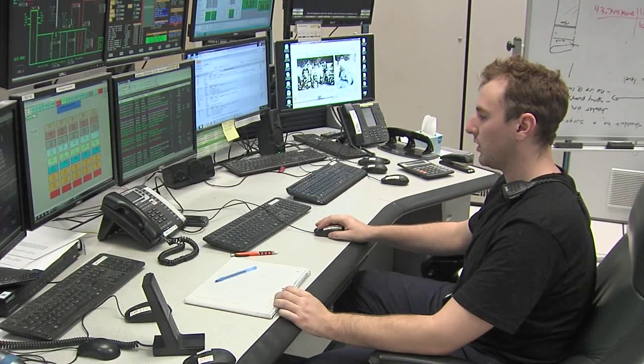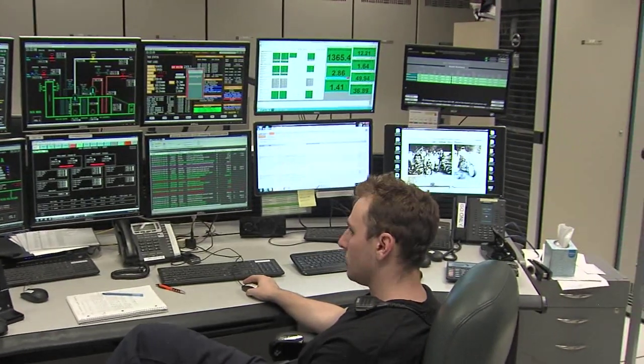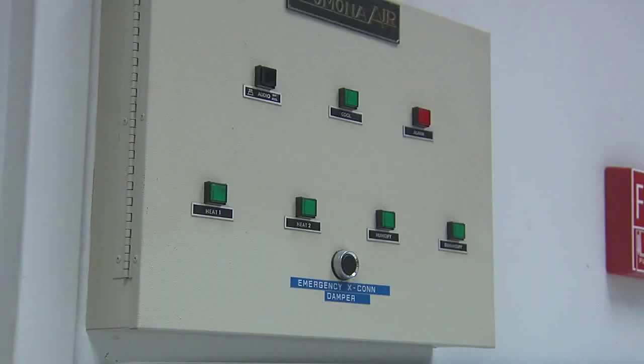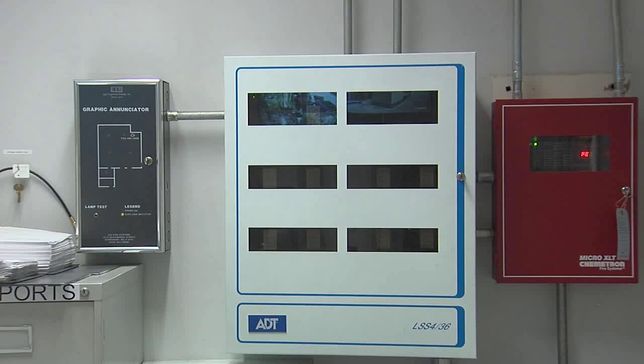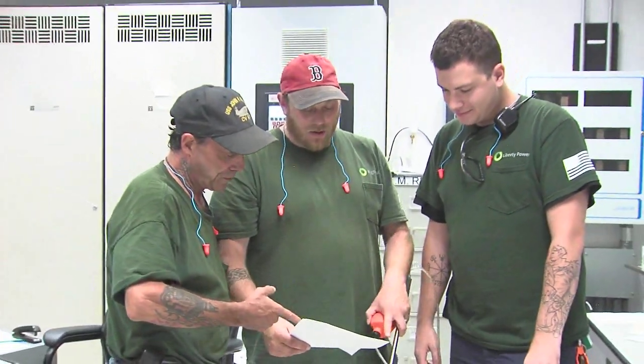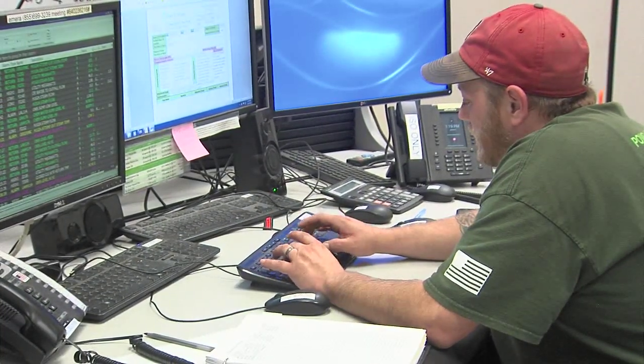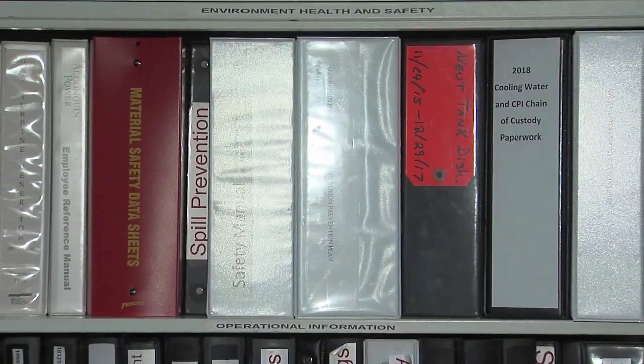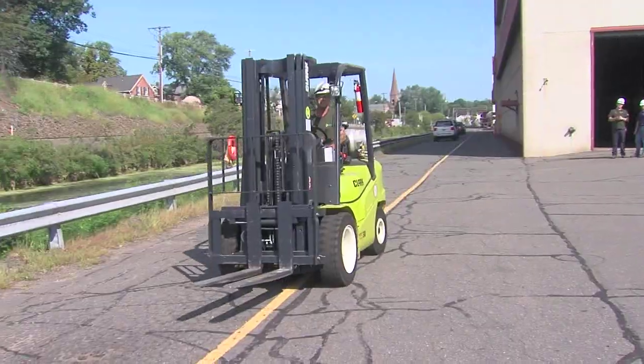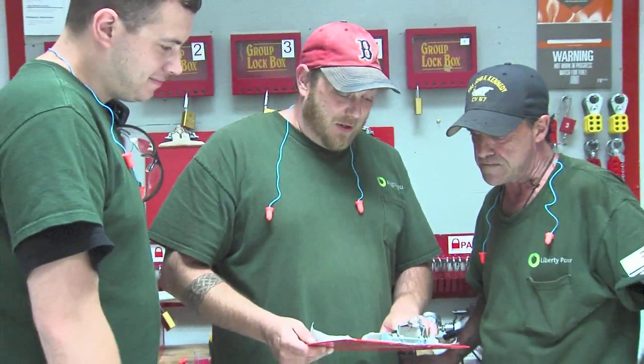This is the control room. It serves as the plant's Emergency Operations Center and is staffed 24 hours a day. Entry into the control room is prohibited except when required in the course of conducting approved business, work, or in the case of an emergency. When your presence is required in the control room, stand well clear of all panels. It is positively forbidden to touch control equipment, including acceptance and silencing of alarms. The control room is the place to get a tailgate form before any work is begun. The control room operator will issue you or your group work leader a tailgate form before any work commences at the plant. SDSs and environmental health and safety procedures are available for your review in the control room. Only personnel authorized by the control room operator can operate plant equipment. Operations personnel will be made available to secure and operate equipment for you. The control room operator has full responsibility for all work occurring in this facility.